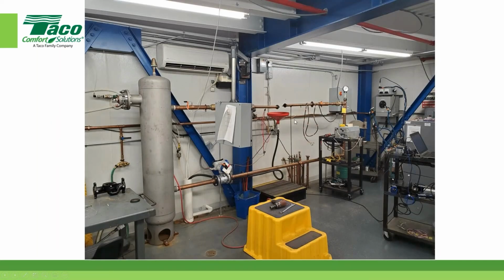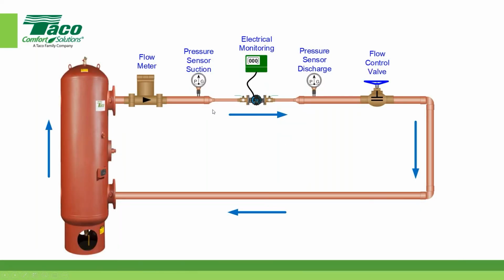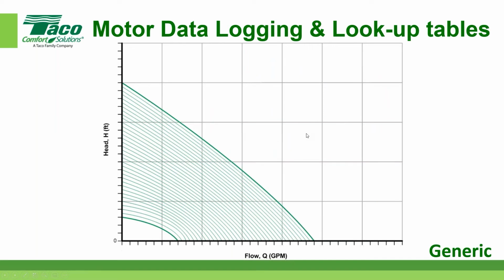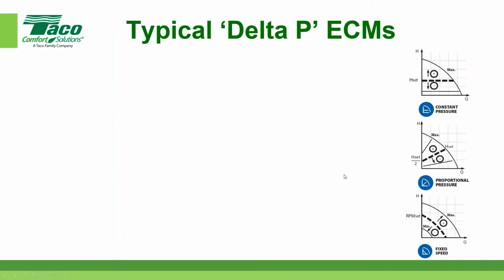Remember that same lab that we talked about? And remember that same mechanism for getting all the information on what the motor's doing? Well, we can record all that and data log that information. Based on running the pump through a bunch of different scenarios, we can log that information onto a particular circulator's curve. So, for instance, if the circulator is seeing a duty point right here, it simply looks down and reads the GPM and looks over here and says, hey, when I was on a test bench, this is what I saw, X amount of GPM at X amount of feet of head, and it spits it out on the front of the unit. So guys, it's not that big a mystery.